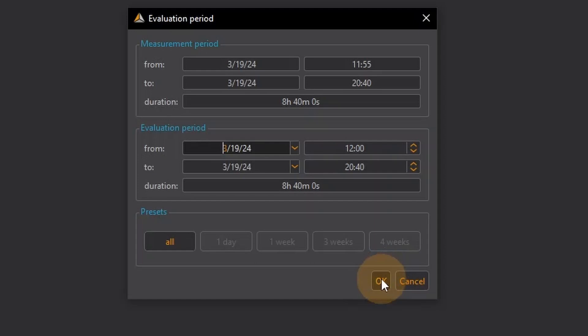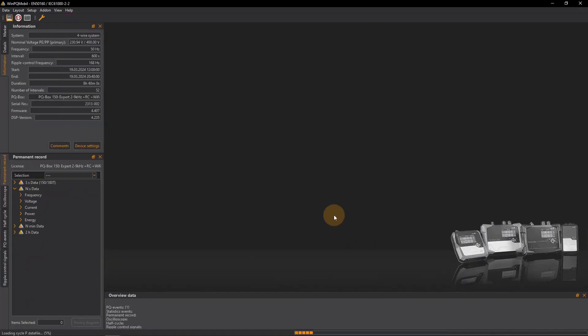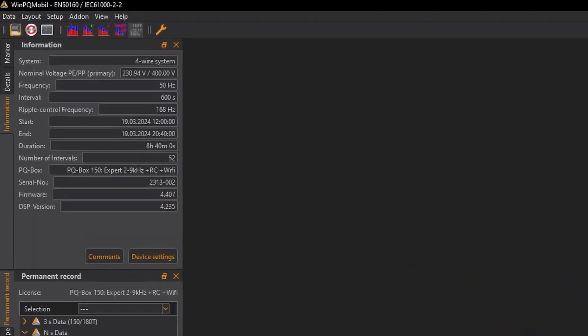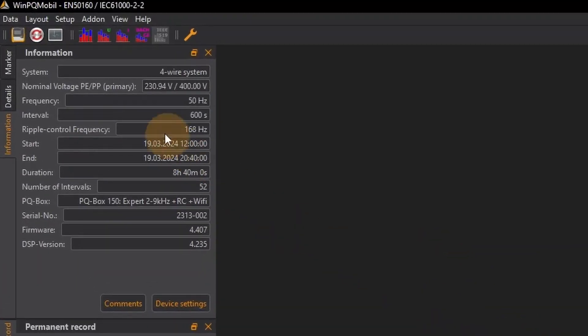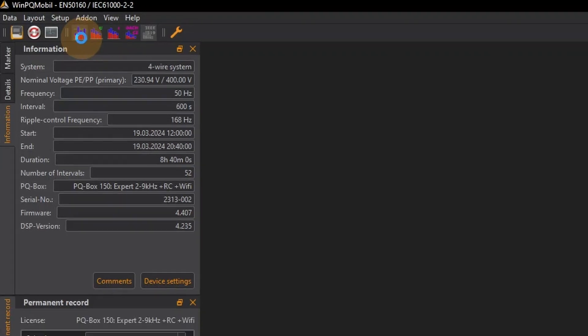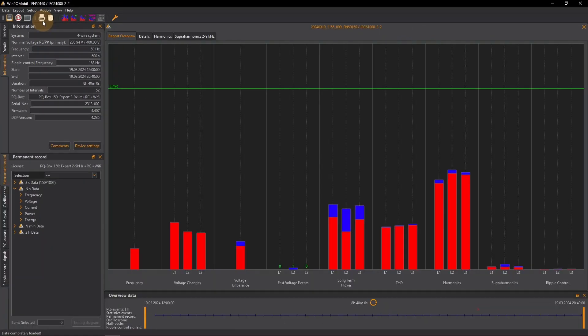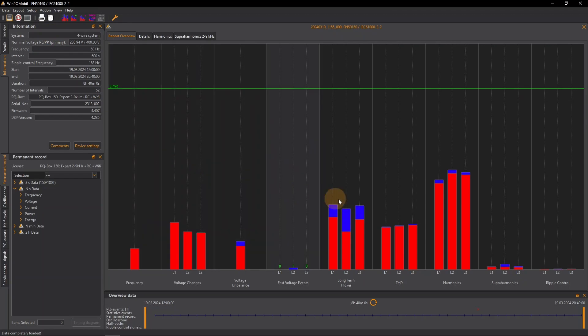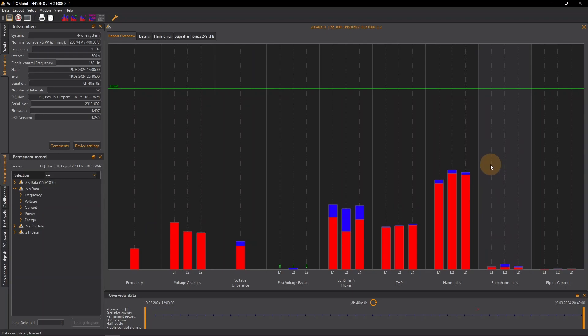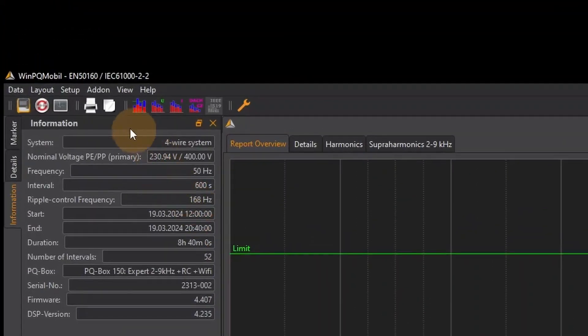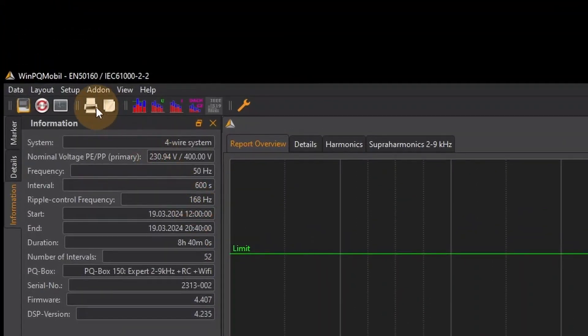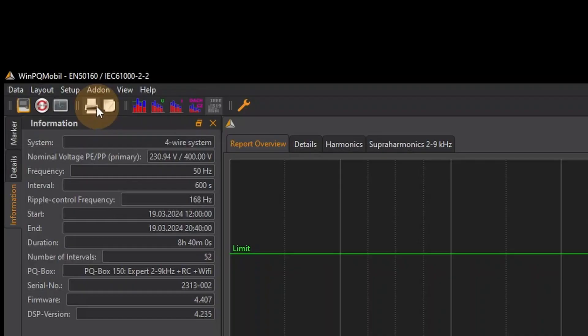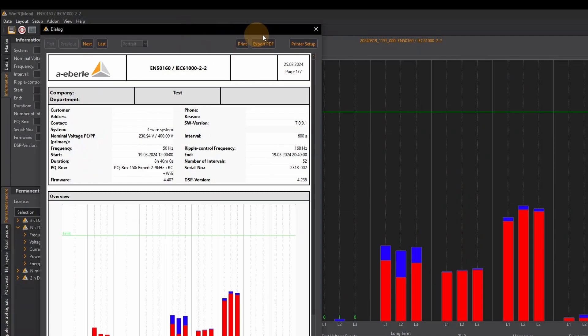I can create a standard evaluation for example according to IEC 61000-2-2 with just one click on the icon with the red-blue bars. WinPQ Mobile shows me an overview of all evaluated measured variables and possible limit value violations. By clicking on the printer icon, I can create a report and print it out or export it as a PDF.